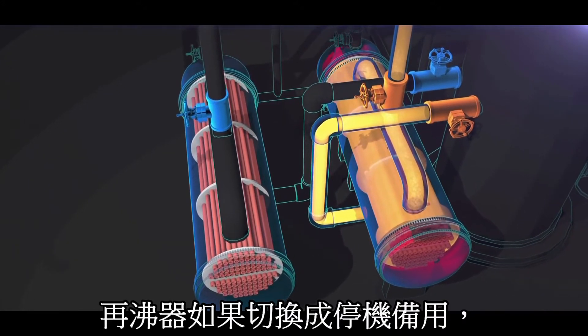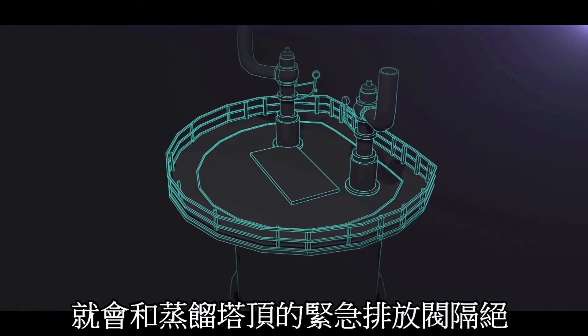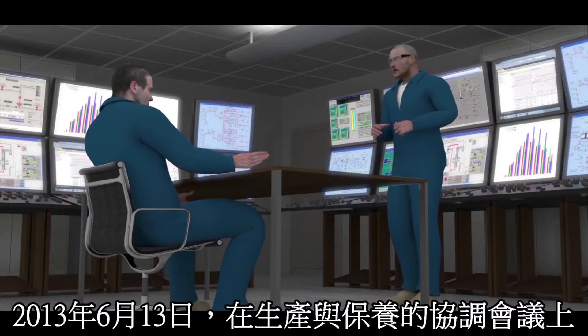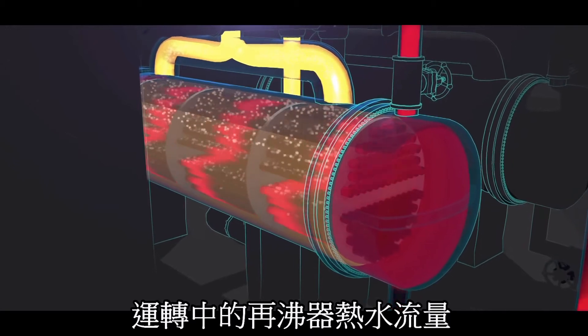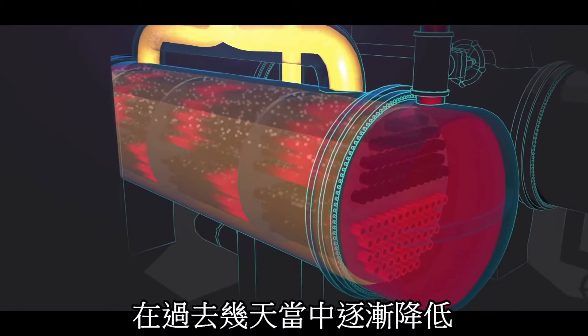They isolated the standby reboiler from its protective pressure relief valve, located on top of the fractionator. On June 13, 2013, during a daily meeting with operations and maintenance personnel, the Williams plant manager noticed that the water flow rate through the operating reboiler had dropped gradually over the past few days.